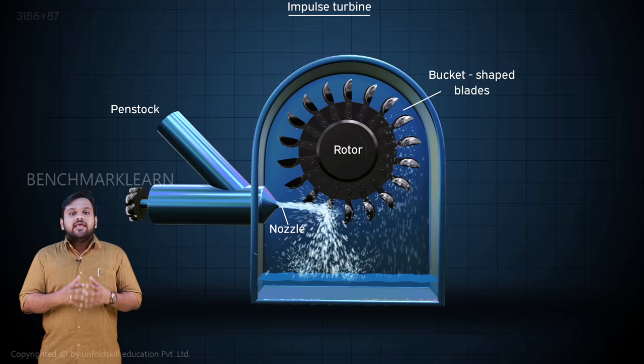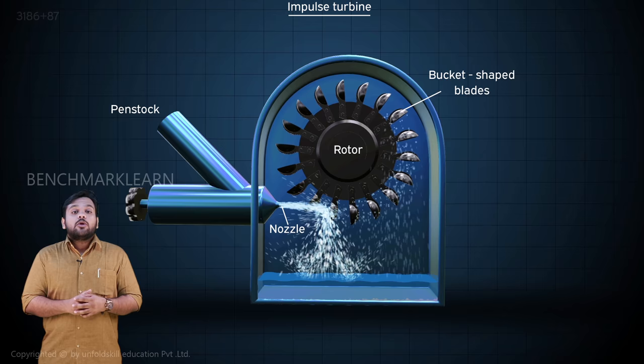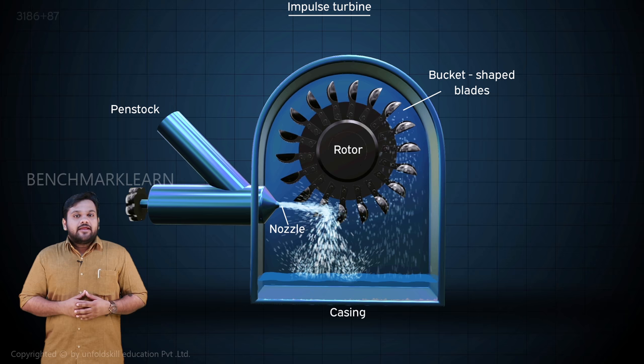In a Pelton wheel turbine, the rotor is connected to a gearbox which modulates and transmits the power to a generator at a specified speed. This produces electricity at the required frequency. The whole Pelton wheel turbine system is enclosed in a casing to prevent the loss of water and also to protect the components from the external environment. The water which comes out of the turbine flows through a portion called a race and exits the system.